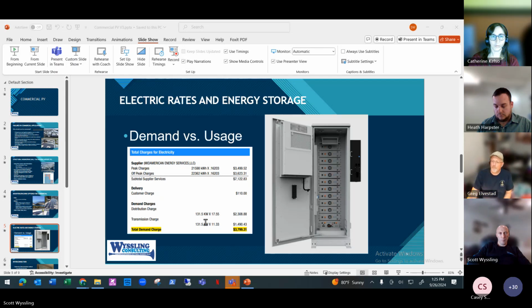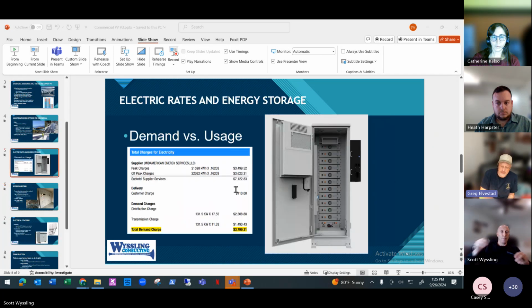And that's pretty significant. One of the ways you can mitigate that, and we've got an example of a storage unit here, is battery energy storage. You can bring those on and provide instantaneous peak demand shaving by tapping into the energy that's stored in these batteries to shave the peak off. And there are calculations that would need to be done to factor in the cost of the batteries and the associated equipment to make the interconnection.